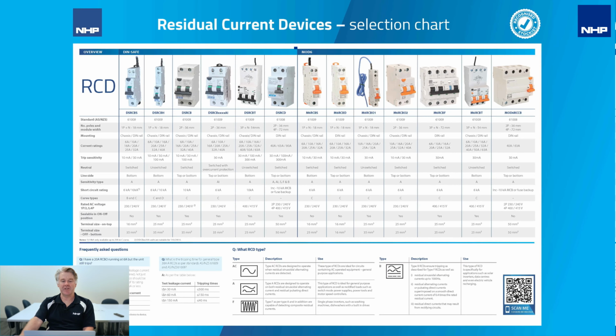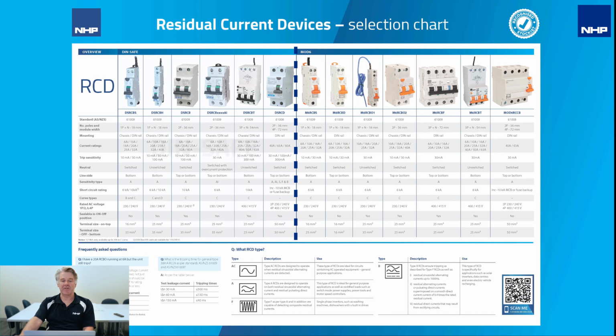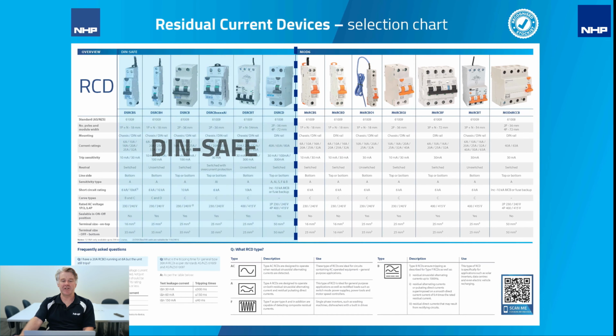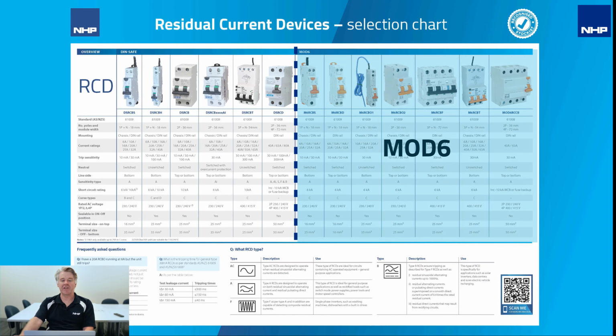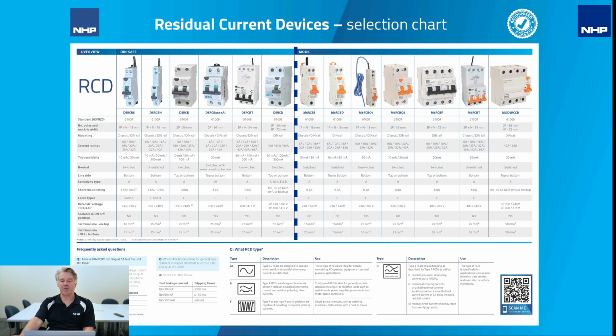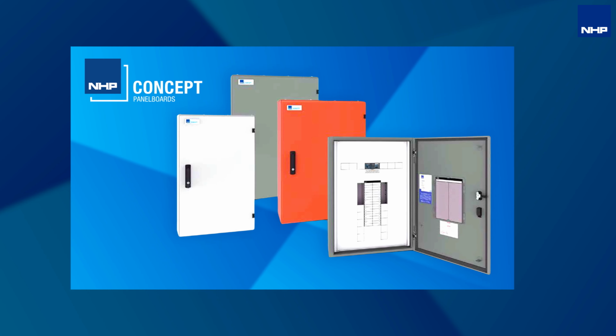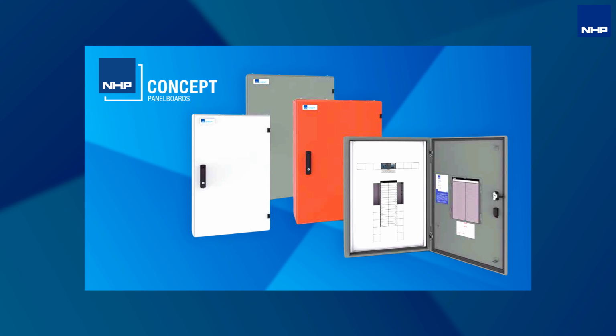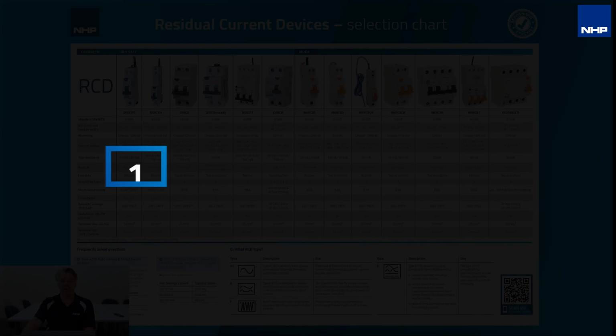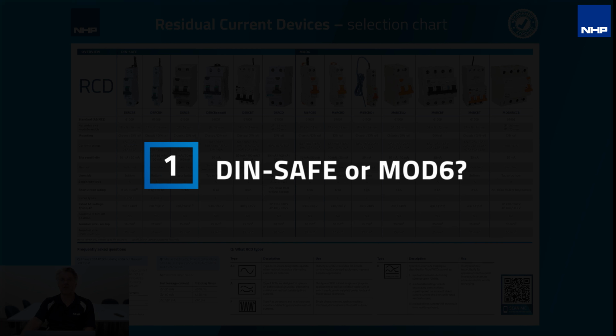On the top here you can see it's split into two. On the left hand side is the DIN safe for the DIN-T type applications, and on the right hand side we have the Mod 6 type applications. So depending on what application you're using or what enclosure type, the DIN-T or DIN safe is primarily for the concept panelboard range or industrial type load centers. The Mod 6 is more for your residential or light commercial applications. The first selection when choosing is, is it DIN safe or Mod 6.